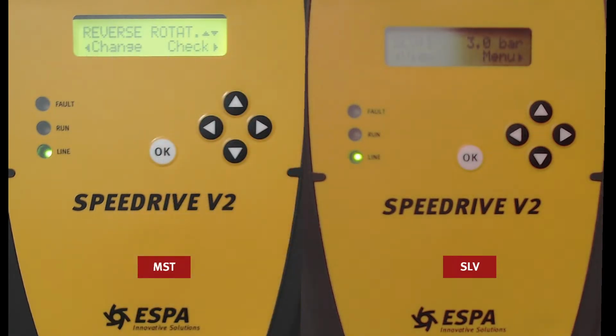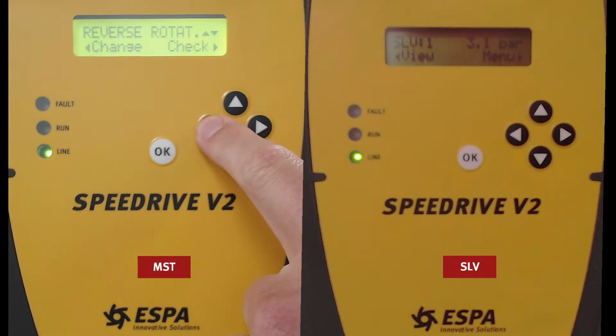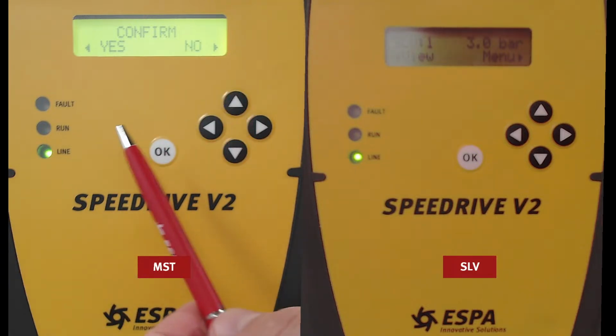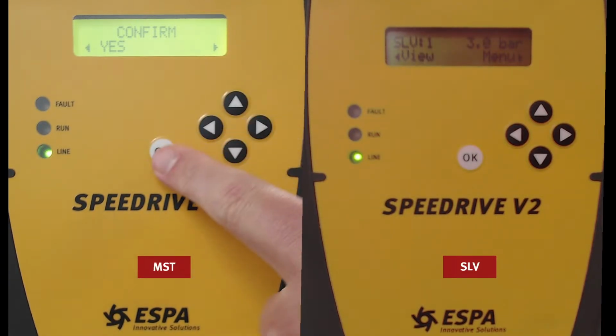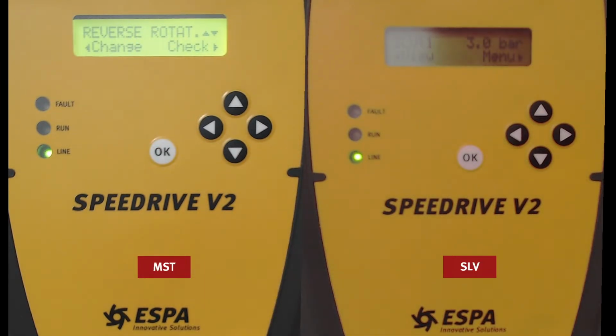Reverse rotation. The first thing that we did at starting was to check the rotation of the pumps, but we can do it also here. In case the rotation was the other way around, turning anti-clockwise, we can change it here, just going through change and confirm yes or no. In this case, pumps are turning properly, so we press no, OK in order to save it, and we can continue. Once changed, if it's the case, we can check over here. We don't have to go out and go up again.